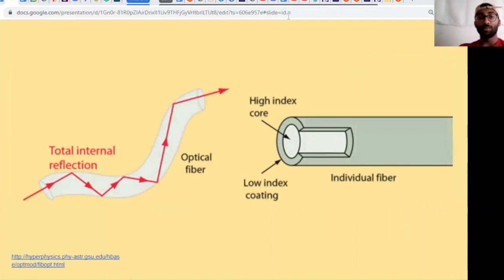An endoscope employs total internal reflection by bouncing light from one end of the optic fiber bundle to another. Total internal reflection happens when you bounce light waves from a medium with a high index of refraction, such as glass or plastic, to one with a lower index of refraction, such as air. This causes the light ray to bend away from the normal.